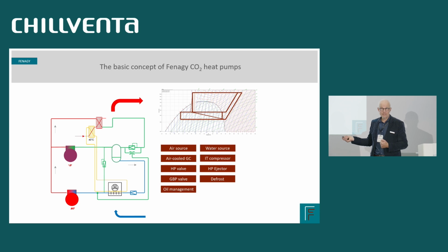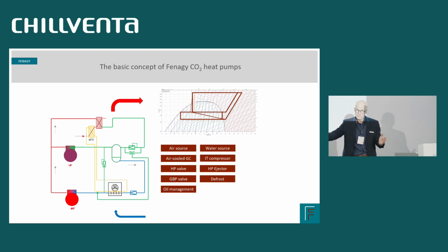And we are then heating the circuiting in the evaporator. Of course, we have to pump it down first. We have to stop the fans before we start to use the hot glycol into separate passes of the heat exchanger. So that is the way we do the defrosting. So the heat pump is still producing heat because we're not defrosting all the sections of the evaporator. We're just taking one section, all the other sections of the evaporators are still running, while when that is defrosted, we continue defrosting the next one.